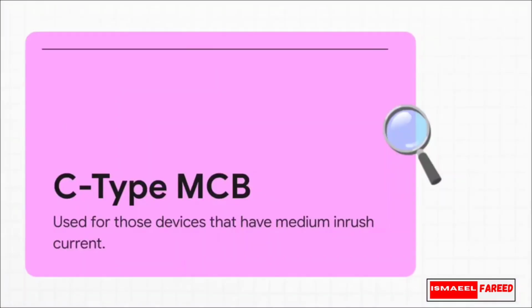So what exactly is a C-type MCB? Simply put, it's a circuit breaker designed specifically for devices that produce a medium inrush current. Think of it like a bouncer at a club that's just a little bit forgiving. It allows for a moderate temporary spike in electrical demand without instantly tripping and killing your power. It lets standard devices power up, but it's strict enough to cut the power if that surge lasts a little too long and becomes a hazard.